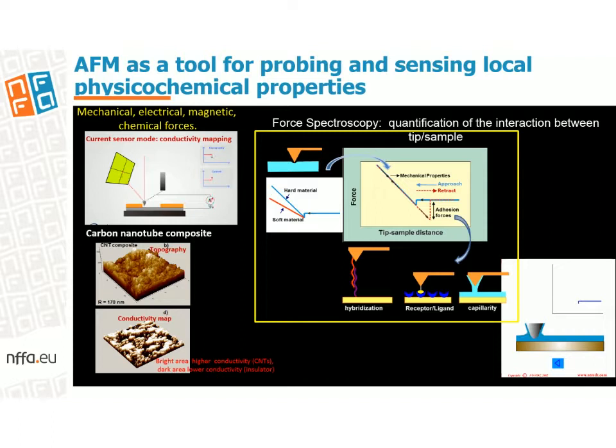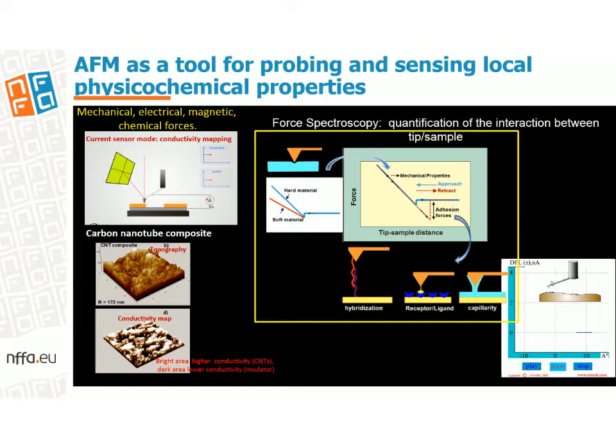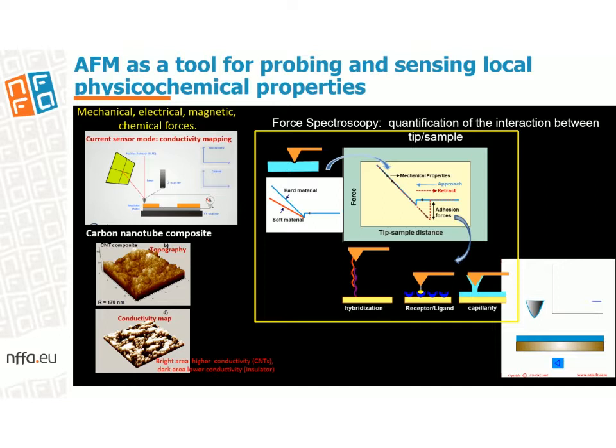Force spectroscopy, which consists in evaluating the forces during tip approach and retraction, allows extracting information of mechanical and adhesive properties. When the tip contacts the sample and presses on it, one can get the mechanical properties of the materials. When the tip is retracted, a hysteresis can appear, since the tip may be stuck to the sample by adhesion forces. Thus, such hysteresis can provide information on hydrophilic-hydrophobic domains, charge interaction, receptor-ligand bindings, acid-base properties, etc.